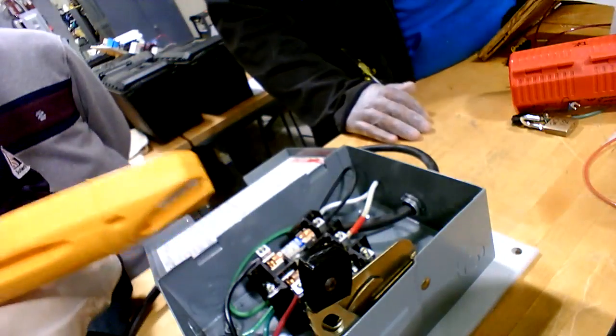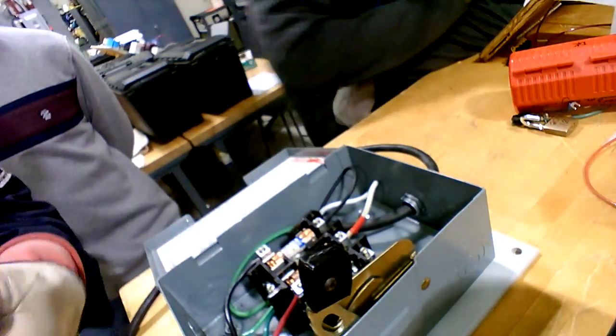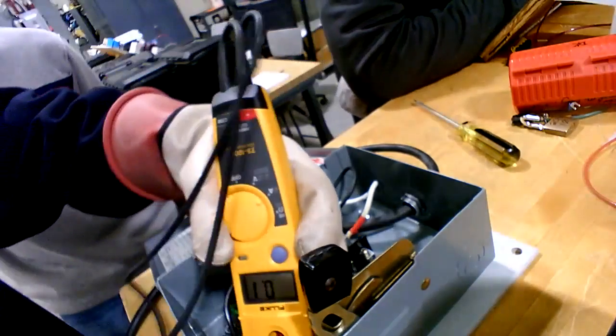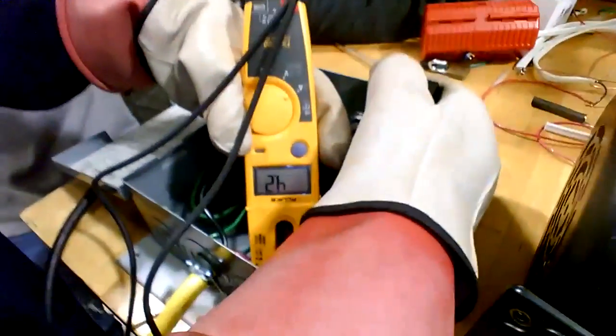The amps. You're going to go to the fork again. When you're checking amps, you're using that fork to check it. When it's a magnetic pickup, you don't check it with the plug. Exactly. You'll see it go up. How high did you see it go? About 15. It's around 15 on startup. See it jump up. About 13 on startup.